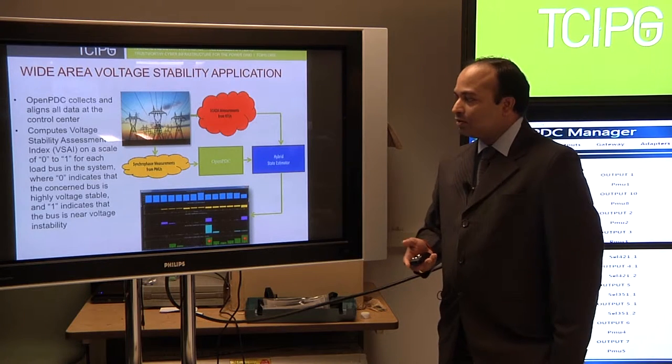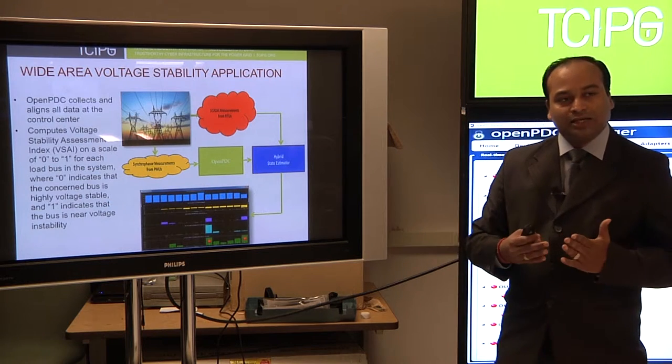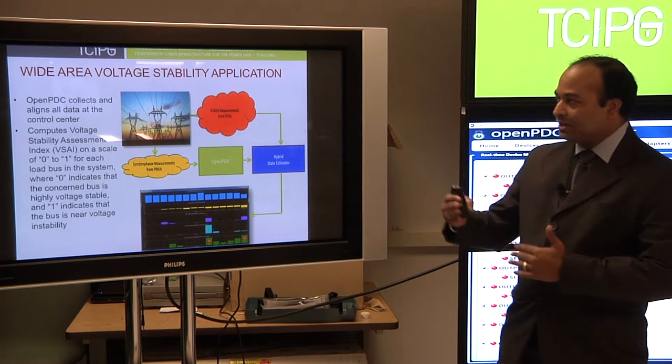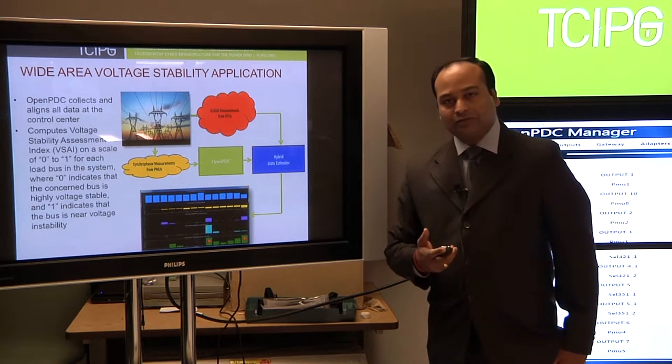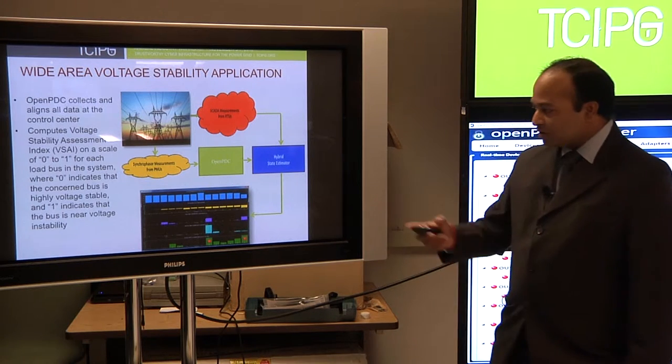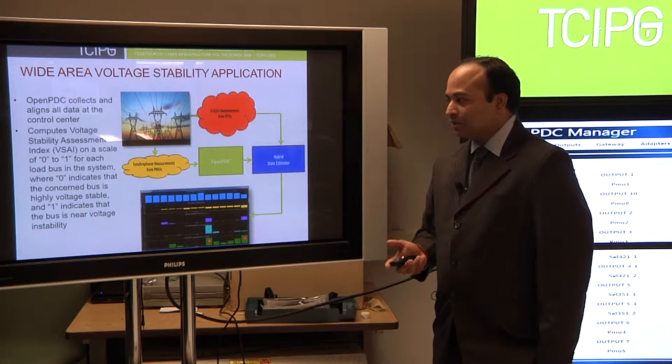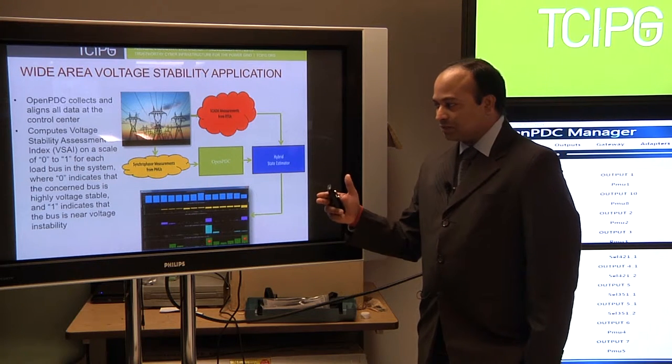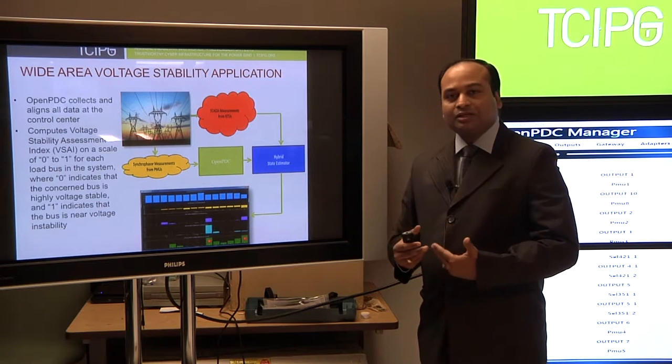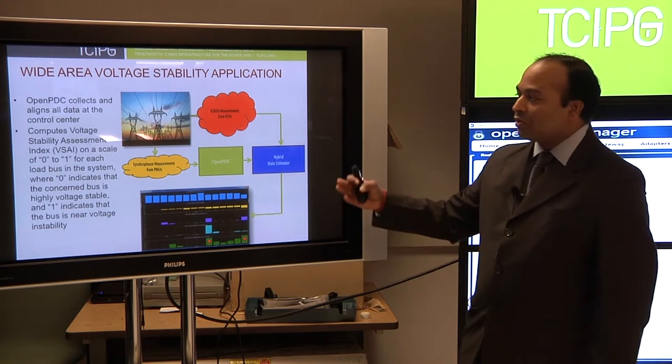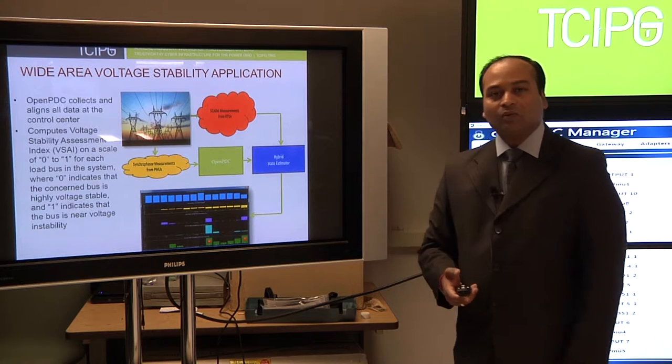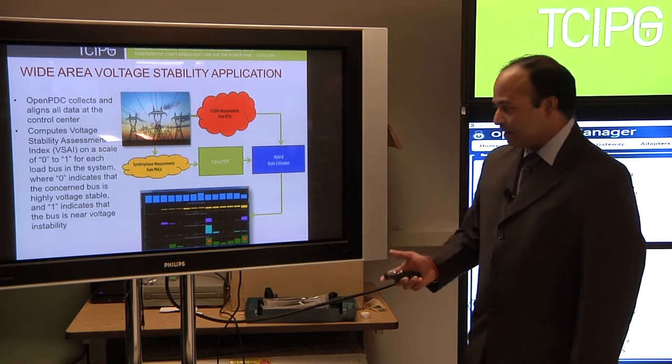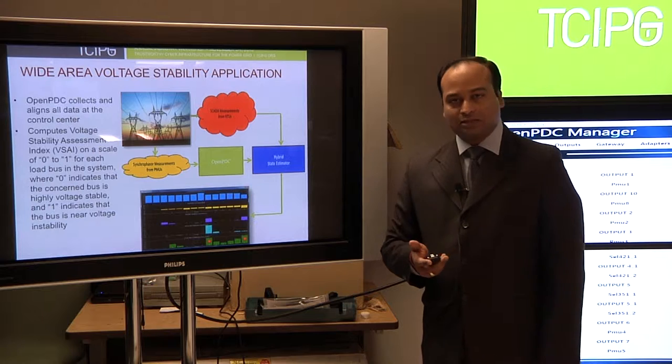Moving on to the application side, once we send the data from SEL PDC, it will be collected at open PDC at the control center. From open PDC, our application, which is voltage stability, will collect the data and monitor the system in terms of index, which is basically between 0 and 1. Zero is good, while 1 is not good. Approaching towards 1 means voltage instability.